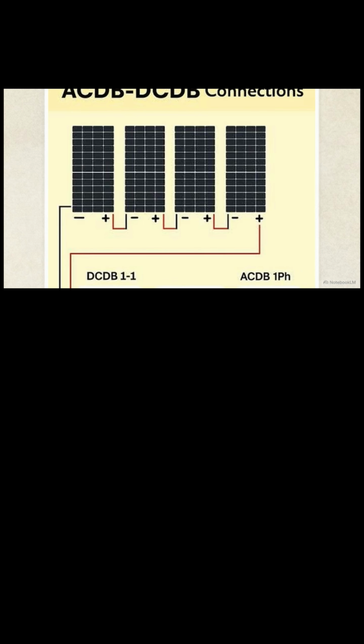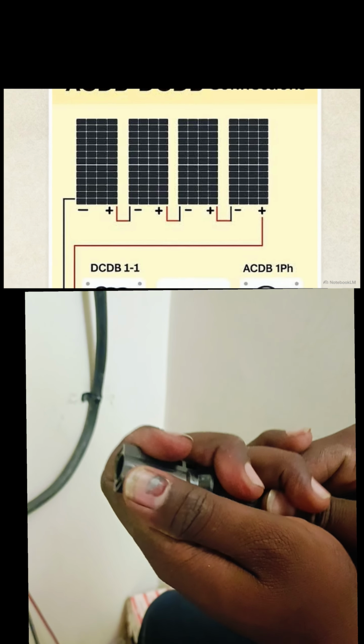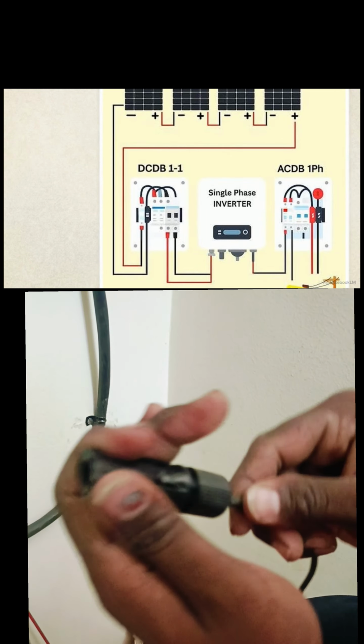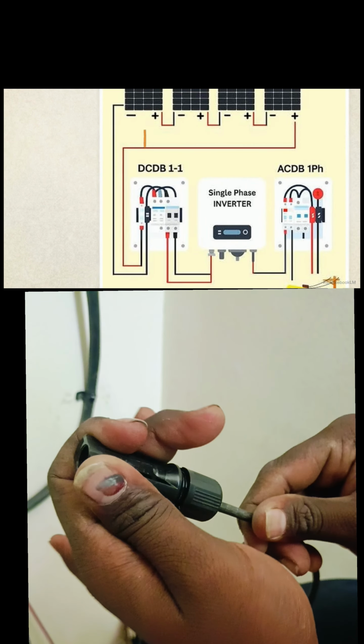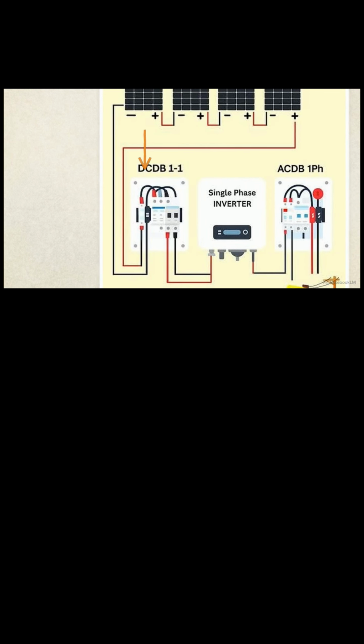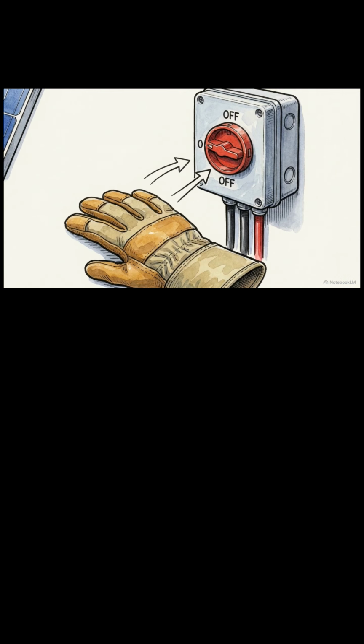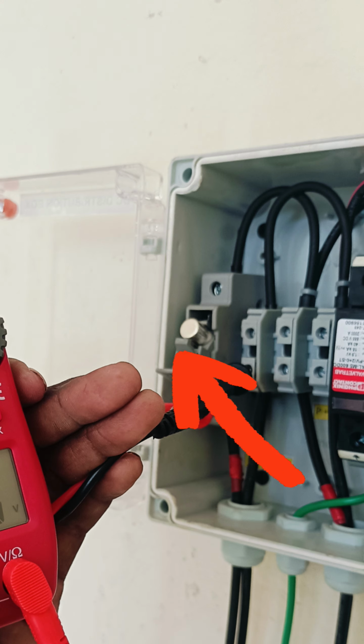We harness power by wiring the 4 solar panels in series, connecting the positive terminal of one directly to the negative of the next. Then, we route the remaining positive and negative leads straight down into the top inputs of the direct current distribution box. Inside that box is your DC isolator switch. You must leave the switch in the off position.